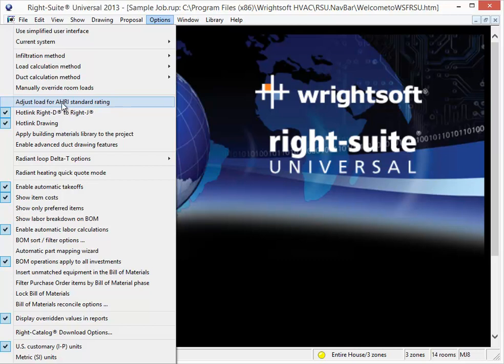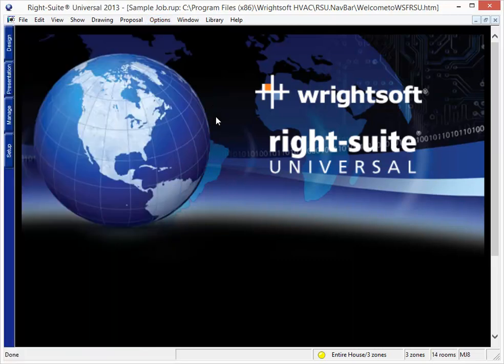This is a feature that will make an adjustment for your outdoor temperature if you're using AHRI data to select equipment. Now, the first rule of Manual S is not using AHRI information when selecting equipment, it's using the manufacturer's information, which will already be adjusted for that outdoor temperature. So I'm going to make sure this is turned off so that I'm looking at the proper numbers.